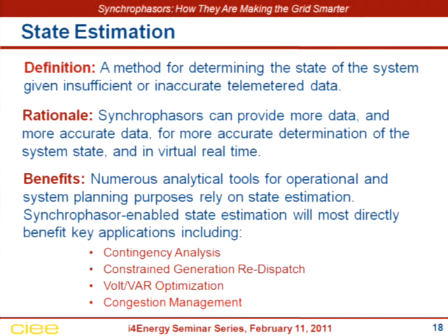Contingency analysis is looking at your system and saying, right now I'm fine, but what happens if this line goes out? It's tripped before—what if it trips again? You can run a quick study and it'll tell you what happens right now, this instant, if that line goes out. If that's a bad thing, you do something to inoculate yourself against it.